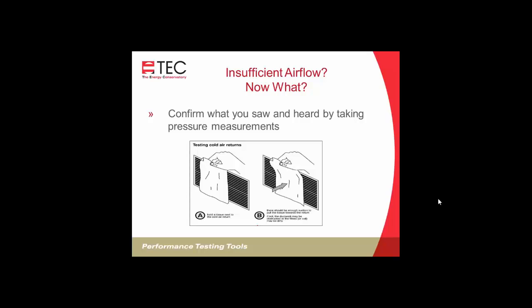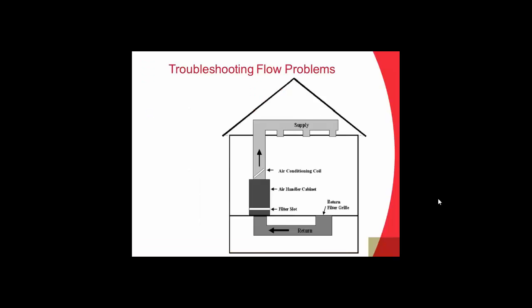So this might be one way of taking some measurements. Maybe not a calibrated one, but holding a tissue up in front of a return. And people do this with bath fans too, just to see, is it getting any airflow? You don't know how much, but at least you know it's getting some. So we'll go through some troubleshooting that you can do to see where your problems might be.